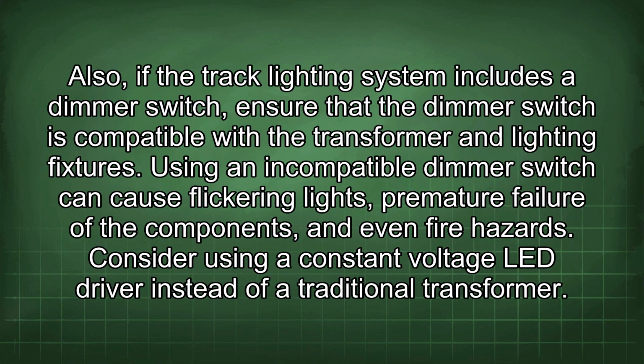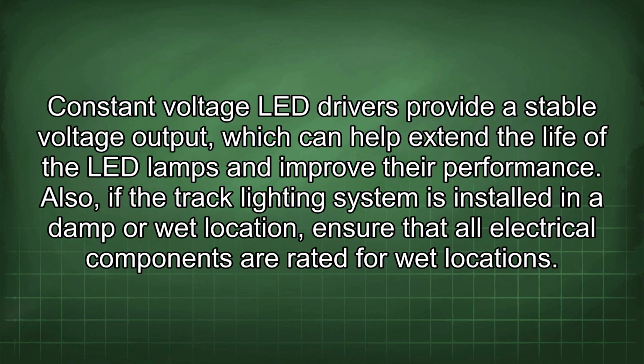Also, if the track lighting system includes a dimmer switch, ensure that the dimmer switch is compatible with the transformer and lighting fixtures. Using an incompatible dimmer switch can cause flickering lights, premature failure of the components, and even fire hazards. Consider using a constant voltage LED driver instead of a traditional transformer.